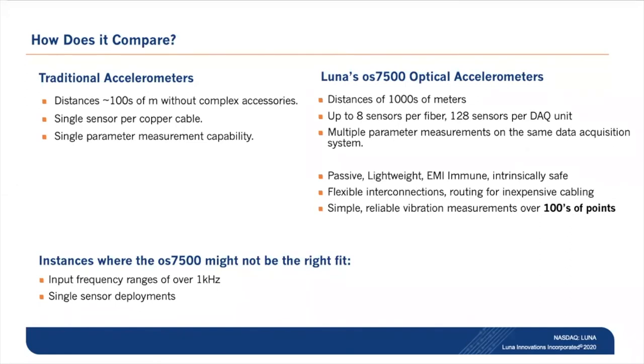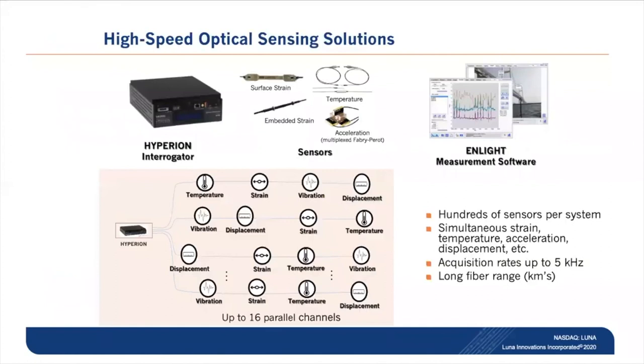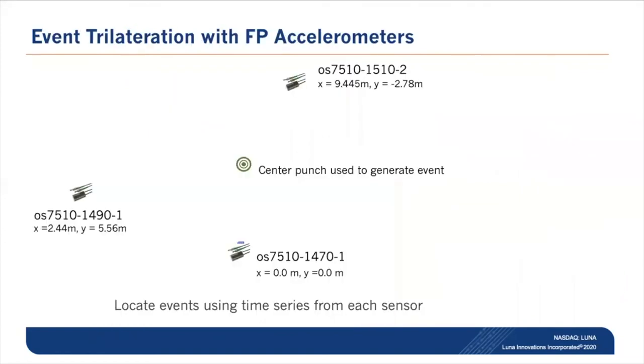There are places where the OS 7500 Fabry-Perot accelerometer might not be the right fit — for input frequencies over a kilohertz or single sensor deployments. We support FBG and Fabry-Perot sensing on the Hyperion interrogator, offering strain, temperature, acceleration, and displacement measurements wrapped in software called ENLIGHT. The sensors don't need to be segregated onto a particular channel — you can have strain gauges, temperature sensors, and displacement gauges on the same channels.